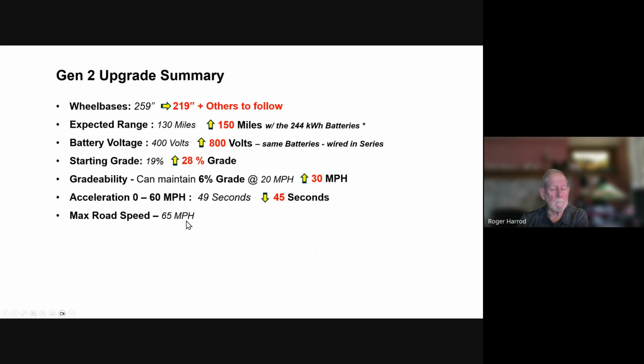Max road speed was set at 65 miles an hour, and it was somewhat difficult with Gen 1 to change that. There were some procedures we did that would make that different. The newer units from the factory, you can set anywhere from 45 to 75 in 5-mile-an-hour increments, so I could get 45, 50, 55, 60, any of those numbers. You could set that up as your max road speed.